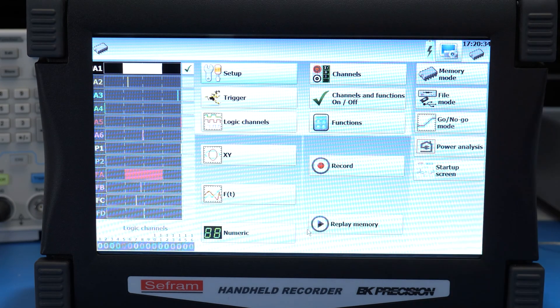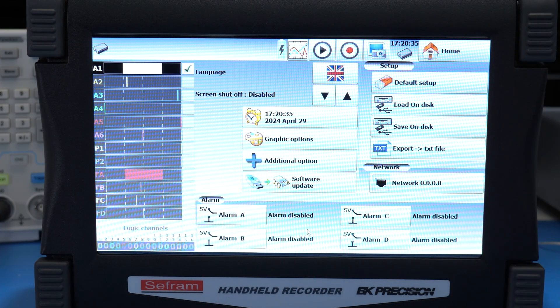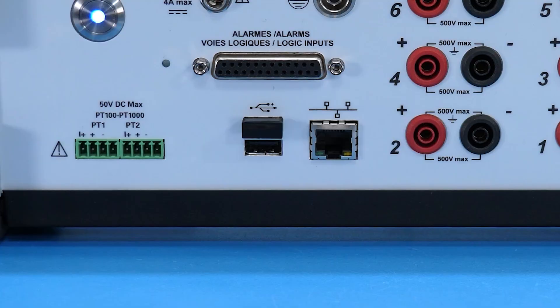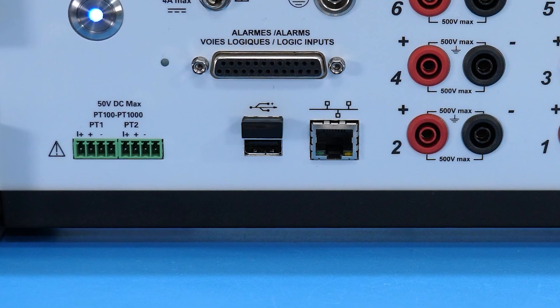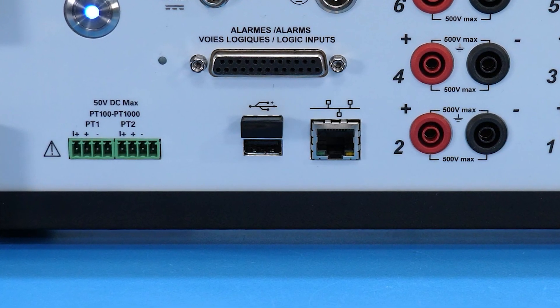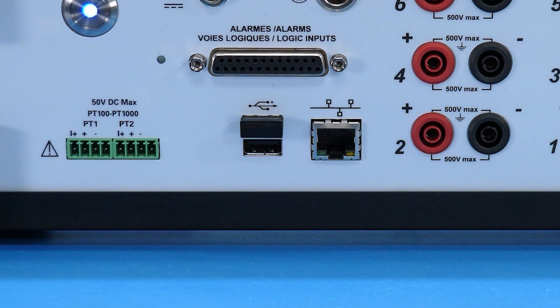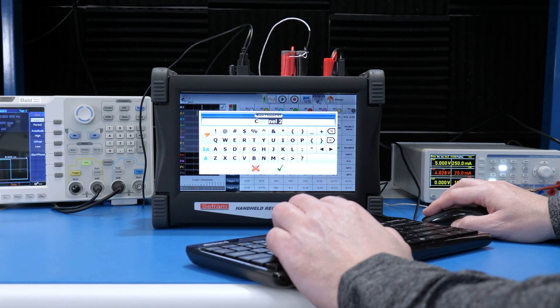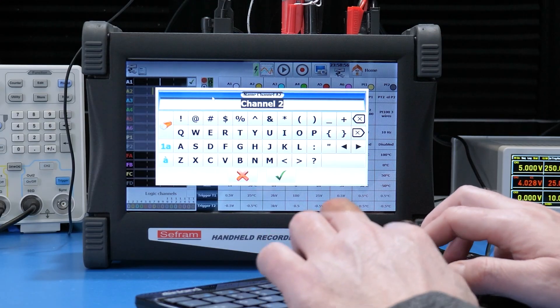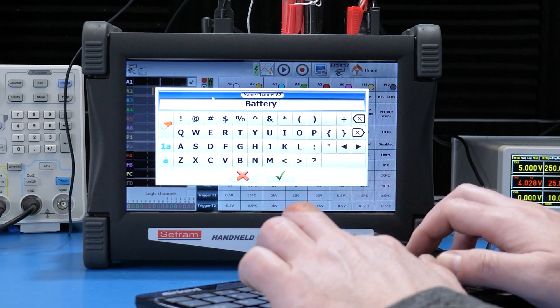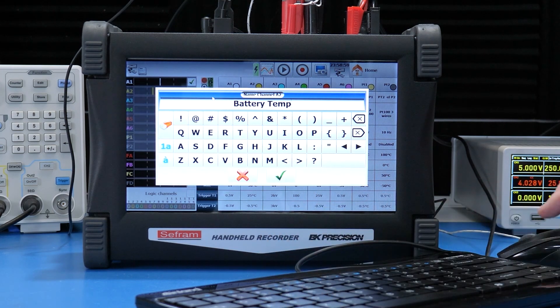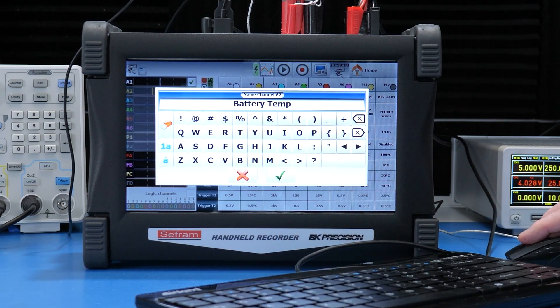The user interface widgets are all very large, so they're easy to see and touch. The unit has a built-in ethernet port, and it has two USB host ports. So, you can plug in a mouse and keyboard, which is helpful when setting up names of channels or math functions to be more descriptive for a specific measurement.